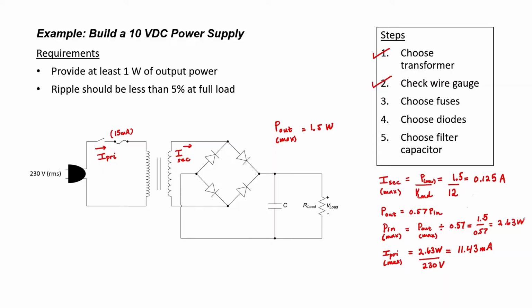were too low, then the power delivered would start to grow. The current through the secondary would start to grow, but the current through the primary would start to grow too. So although the secondary side of this particular circuit is not protected, it's effectively protected because any surge of current on the secondary side would cause a corresponding surge of current on the primary side too. If we were going to add a fuse to the secondary side, then we would want to put it right here, adjacent to the transformer, and I think a 175 milliamp fuse in this situation would be just fine.